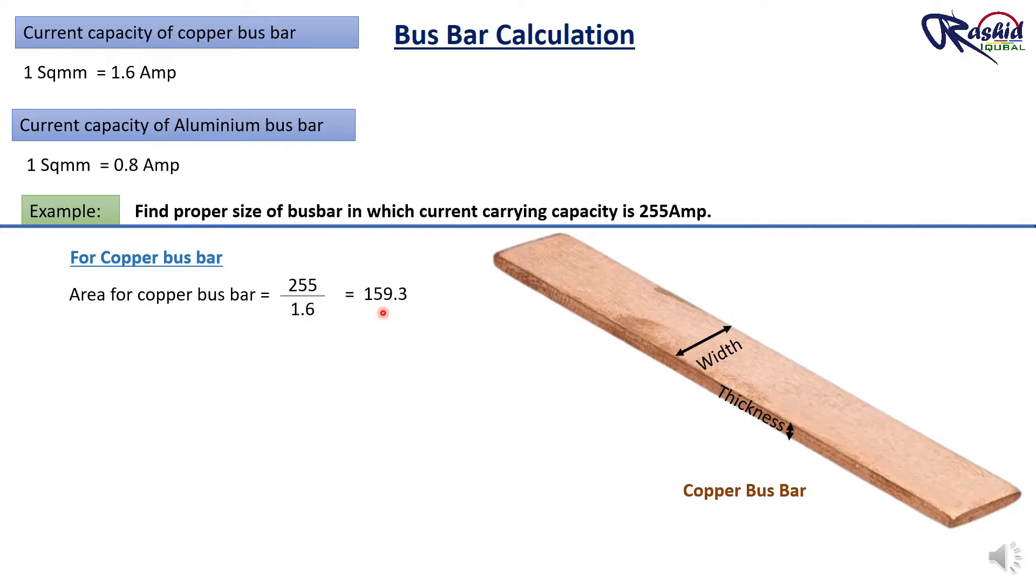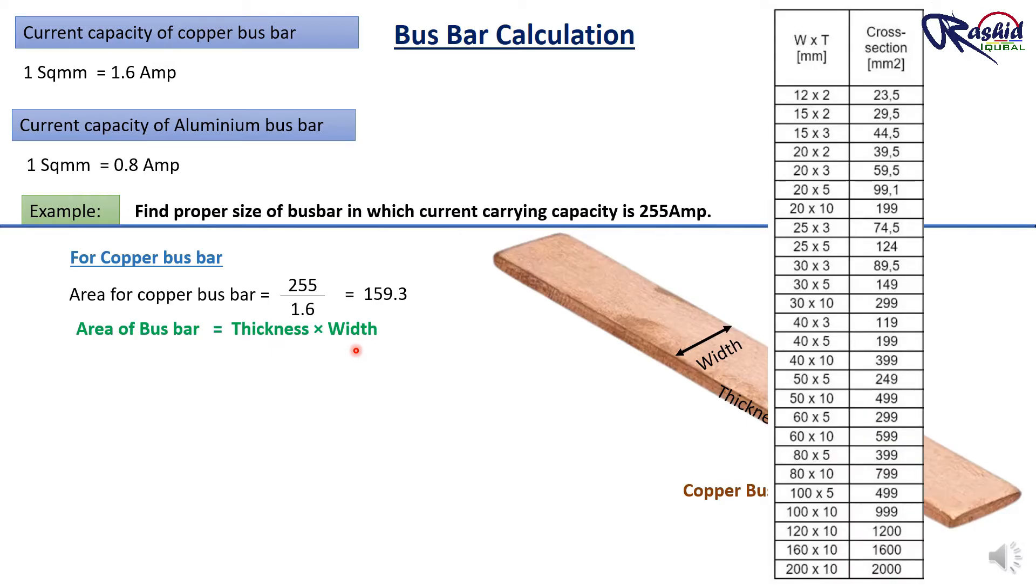Now to find the suitable size of copper busbar, we use this formula. Area equal to thickness multiplied by width. Through this busbar size chart, we can select thickness of busbar. I am selecting here 10 mm thickness. Because this is the standard thickness of busbar which can generally be used in electrical panel. Or you can select thickness as per current capacity.